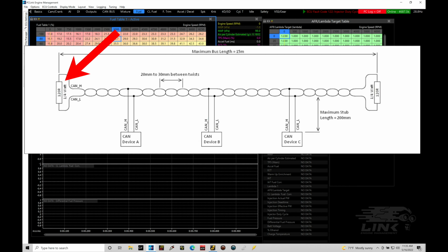We'll talk about how we have this terminating resistor and working with it when we're dealing with the G4X and a couple of devices strung to it in the next schematic, but let's just keep going in general terms looking at the wiring. Now, one thing about the 120 ohm resistor, it needs to have a quarter watt rating or higher. The actual resistance, though, has to be 120 ohm. That is going to be specific.